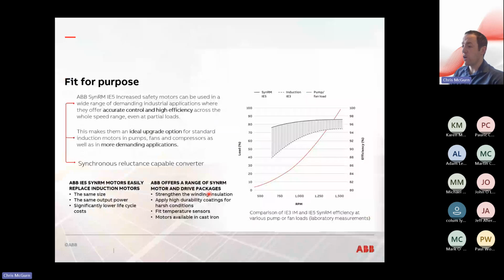So earlier I was talking a little bit more about running at part load when it comes to your motors. Any motor that you have will have a nameplated efficiency stated on the nameplate itself. That efficiency is based on 100% load at 100% speed. But like I say, very few systems, very few applications actually run at that load and speed. Typically, you're running at 70%, maybe even further down.